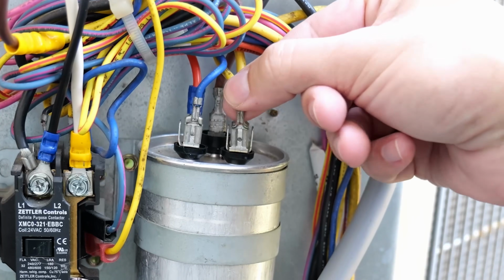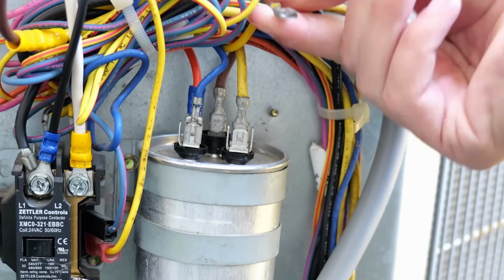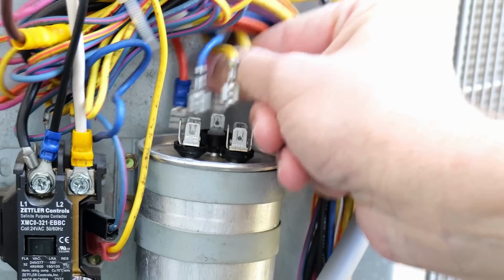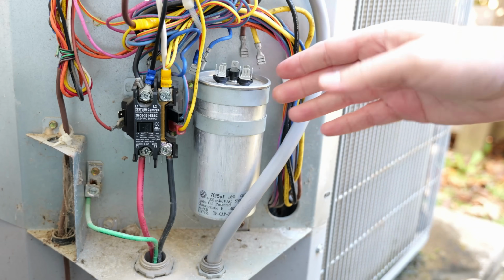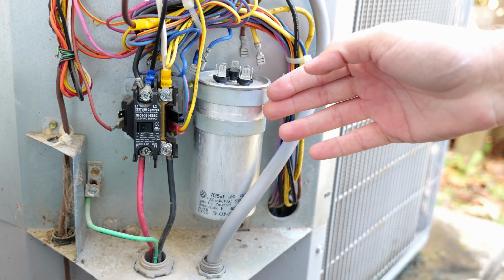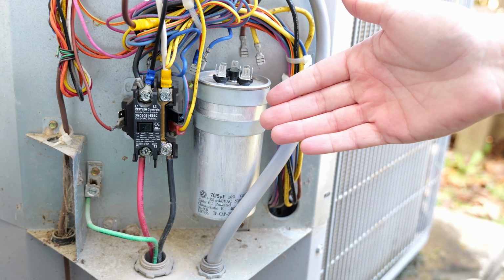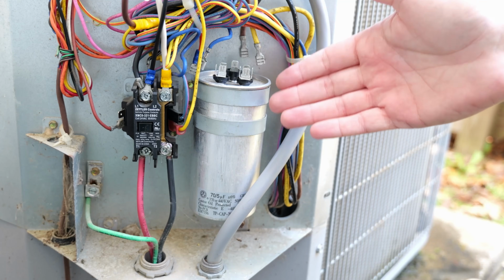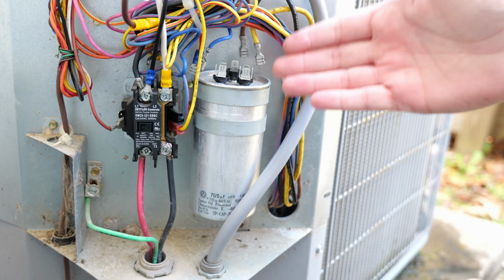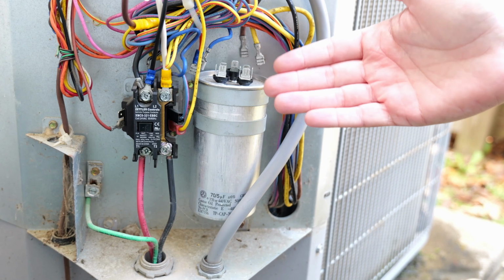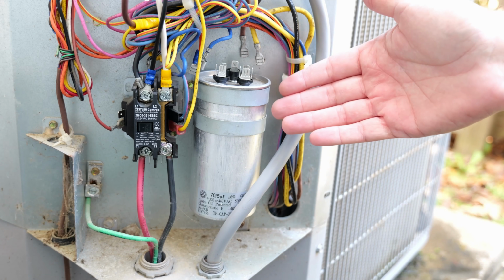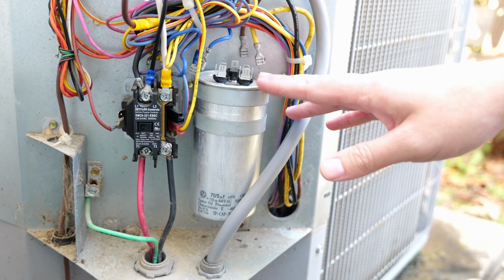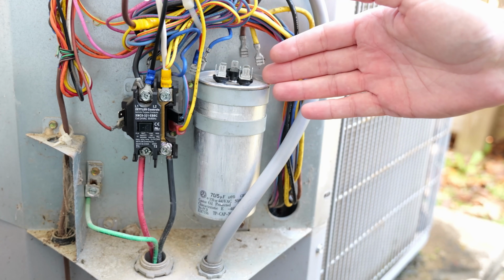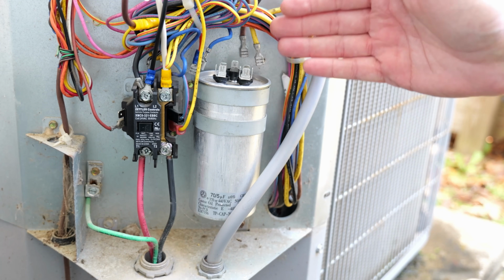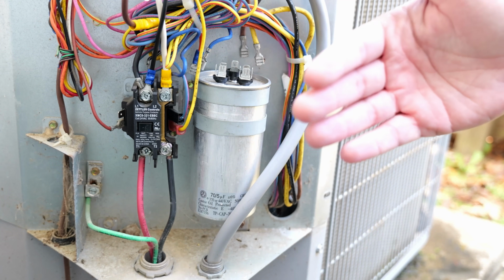So I've already got my pictures, so I'm going to go ahead and start removing my wires from each one of the terminals, and so now I'm ready to take my readings. Now I will just tell you that this capacitor, I don't expect it to be bad because it's been running perfectly fine, but I'm going to find out with you what condition this is actually in. And this is something I actually like to do on at least a yearly, if not semi-annual basis, just to make sure that I'm staying ahead of things and try to catch it as it's going bad before it actually does go totally bad and my AC unit just doesn't work at all.